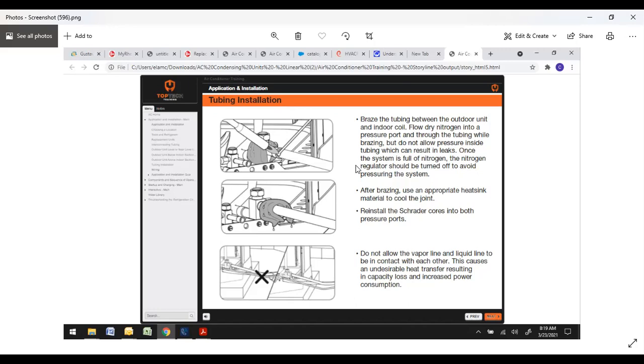That's what's going to lead to, or used to lead to, piston failures. You don't see pistons that much anymore, but that will lead to piston blockages. It'll end up with clogged screens. It'll also cause failed TXVs. Expansion valves have enough problems on their own. Adding to it with additional debris and issues won't help your situation any.